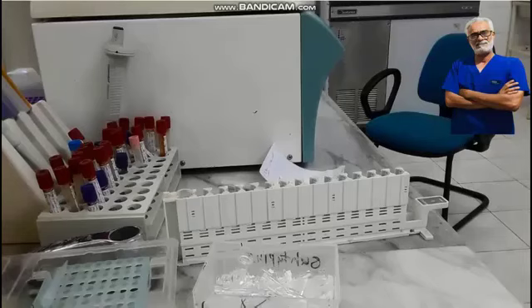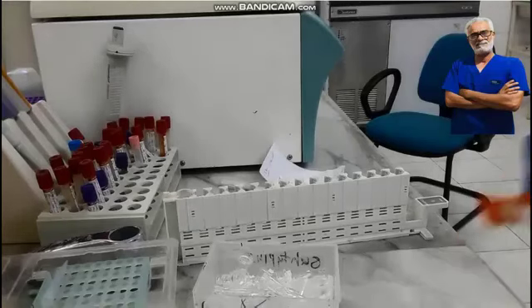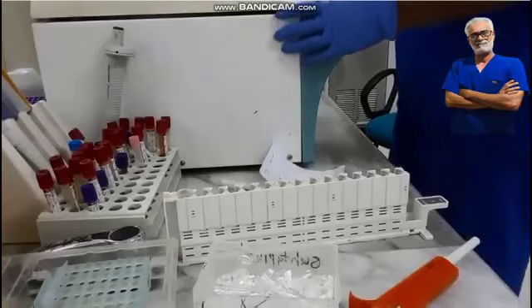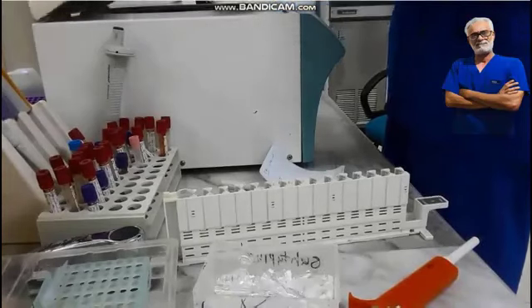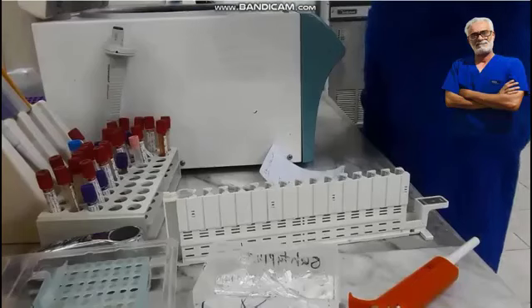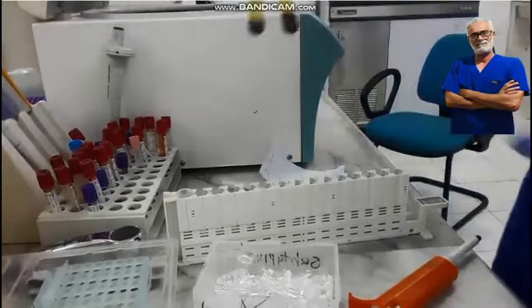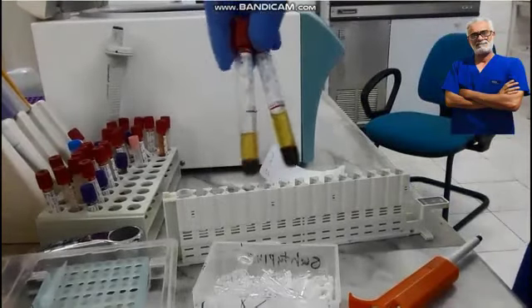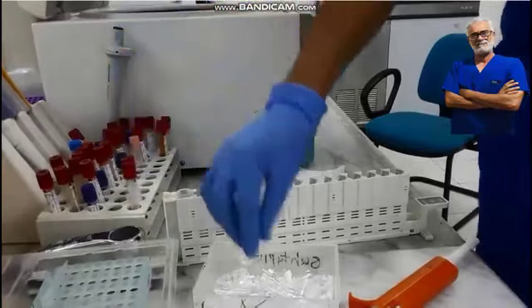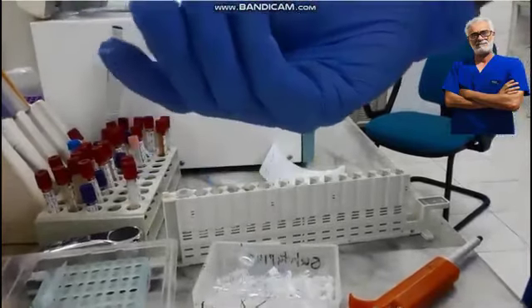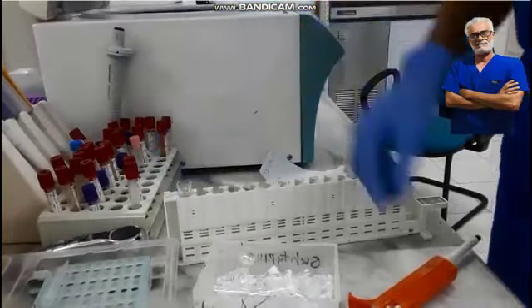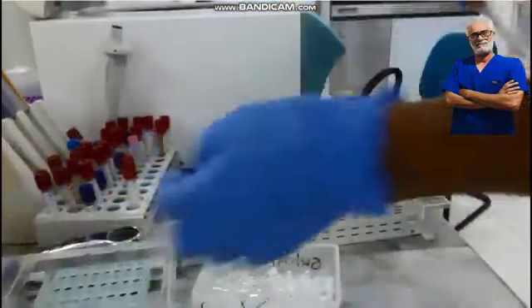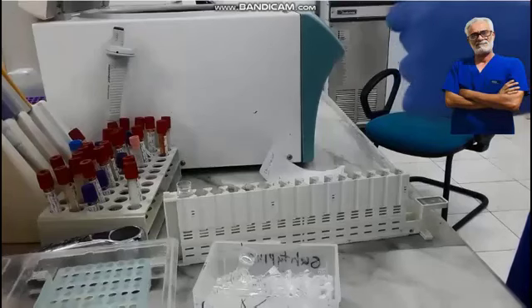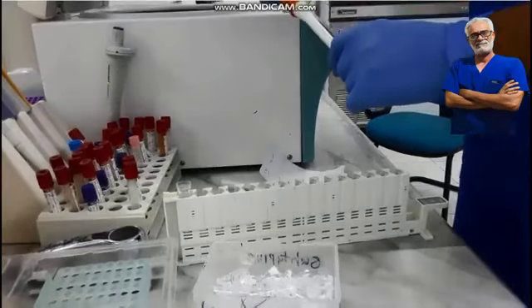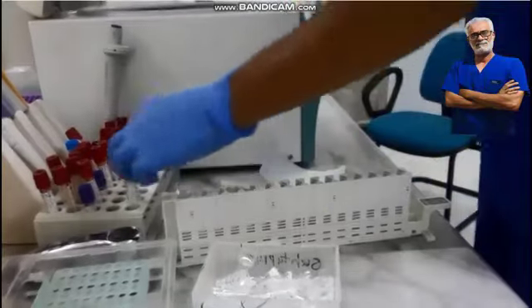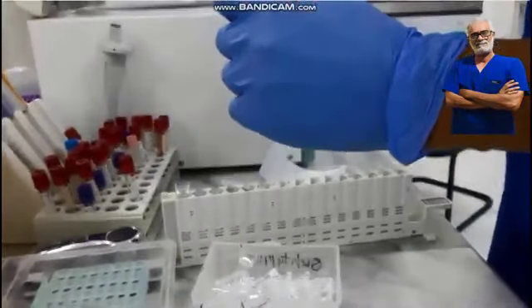As you can observe here in the video, we are using these specific, small, and transparent sample cups. These cups are specially designed by the manufacturer to fit perfectly into the Integra 400 Plus sample racks. Very carefully, and with a steady hand, we begin to transfer the separated sample into the cup. Please pay very close attention to this point. The sample volume is a key factor for a successful run. You should always aim for a volume between 300 to 500 microliters as a strict minimum requirement for the machine.